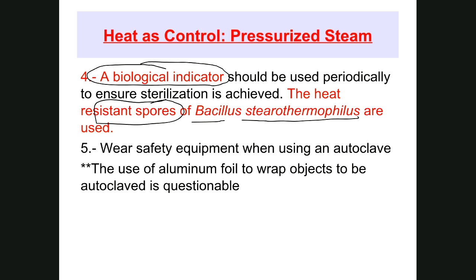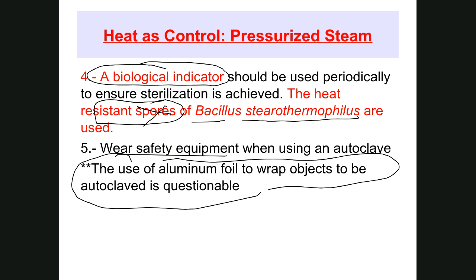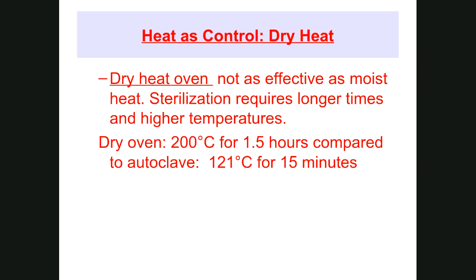If the autoclave destroys these endospores so that they're not viable anymore after autoclaving, then you can say, yes, the autoclave is definitely sterilizing. So that's the means to test the autoclave. Okay, wear safety equipment. And then something that is actually done, but is really questionable, is to wrap things in foil wrap because the foil may or may not prevent the steam from reaching objects. So you have to have an idea of what are the problems with an autoclave.